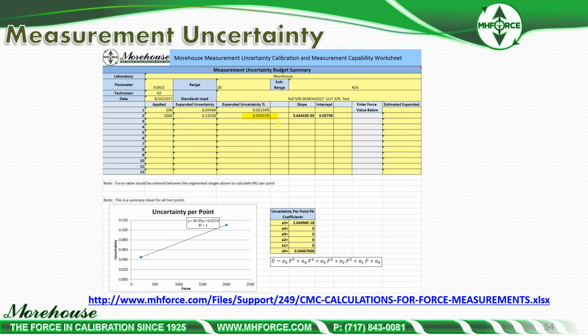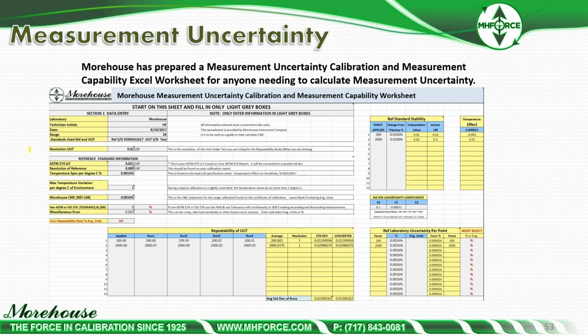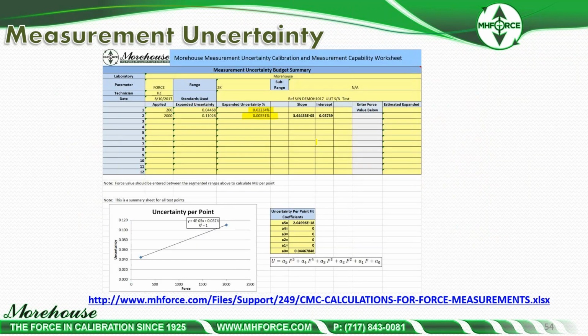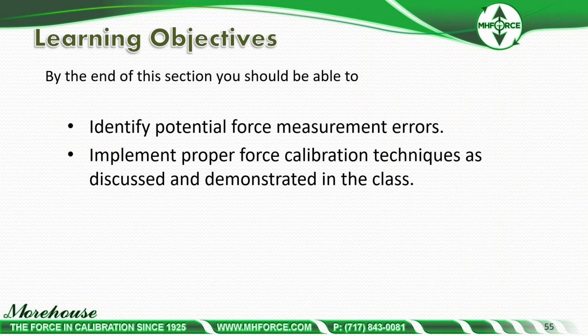At 10%, that should be 0.05, should it not, if we just scale that down? In this case, it's actually lower, but that's all dependent on how good the repeatability is. And if you look at this repeatability, it's darn good. But if we have an inexperienced tech, that repeatability could grow. So there are lots of different factors and contributors that all go together and get weighted. This uses the Welch-Satterthwaite equation, weighted with the appropriate degrees of freedom and everything else. And really, this is a good example that you can't just linearize your 0.005% of full scale. So you really have to run the numbers and test.